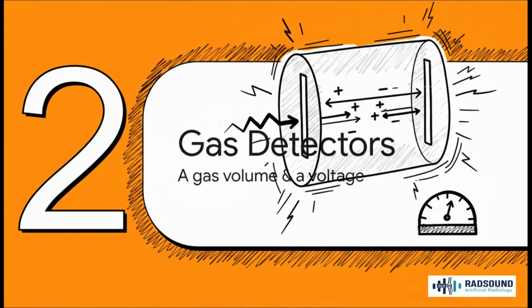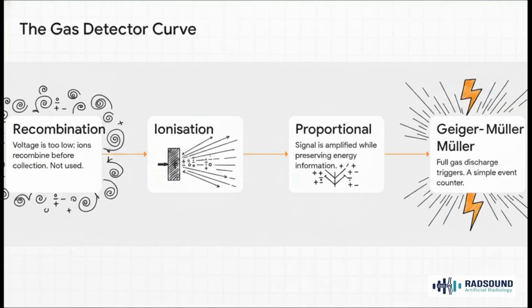At their heart, these are really just a box of air with a voltage. You've got a sealed volume of gas, like air or maybe argon, with two electrodes inside. Radiation comes in, it creates charged ion pairs, and the voltage you apply pulls those charges apart, creating a tiny electrical current. The real magic, and what separates one type from another, is just how high you decide to crank up that voltage. And this curve shows that journey perfectly.